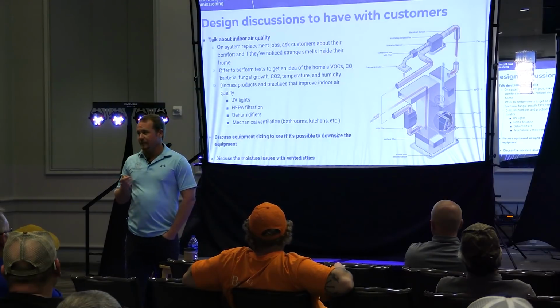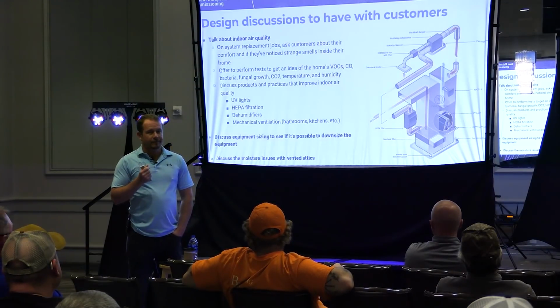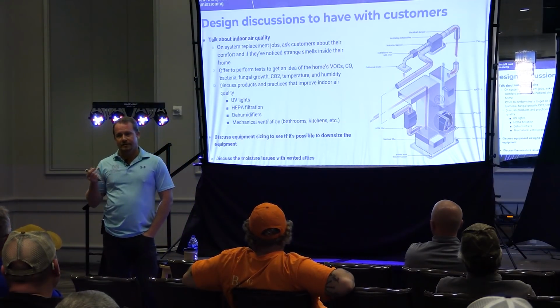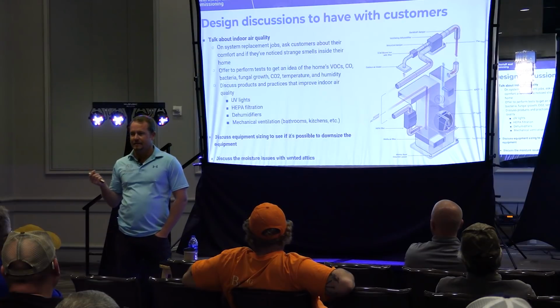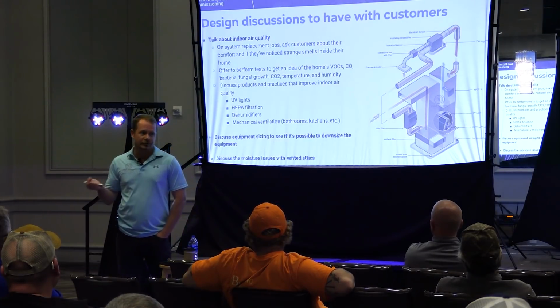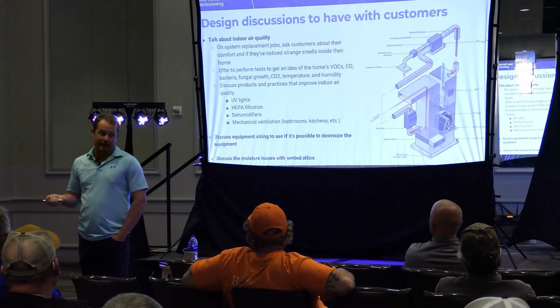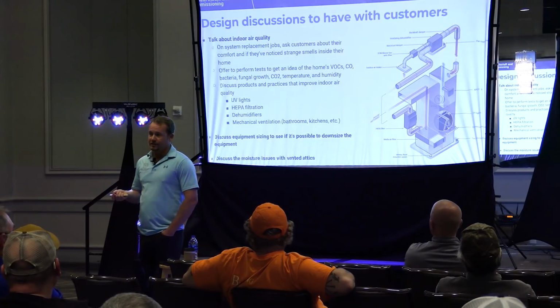It's going to break eventually, that's one thing. Load conditions, partial load conditions, that's exactly it. Because if you design that system, you're designing it so it can cool the structure during the hottest day. So when you're in part load conditions, it's going to struggle.